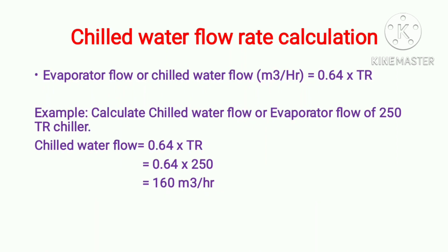First we will learn how to calculate the evaporator flow rate, or chilled water flow rate. The value in meter cube per hour is equal to 0.64 into TR. This is the thumb rule. By using this thumb rule we can calculate the chilled water flow rate in few seconds. We will calculate by taking one example — suppose we have a chiller of 250 TR, and we want to calculate the chilled water flow rate using this thumb rule formula.